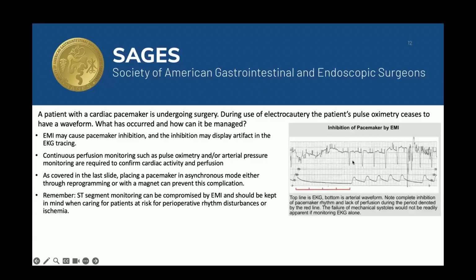And so you can see on the right hand side, there's a segment where the pulse ox tracing drops out, and during which there's this kind of noisy section on the EKG that doesn't really look like heartbeats, but it also looks like something's going on. And so the pacemaker is getting confused, and you're not really getting the patient's heart to beat at all. And so this is kind of one of the scary situations, and this is why we put pacers into asynchronous mode when they are pacemaker dependent.